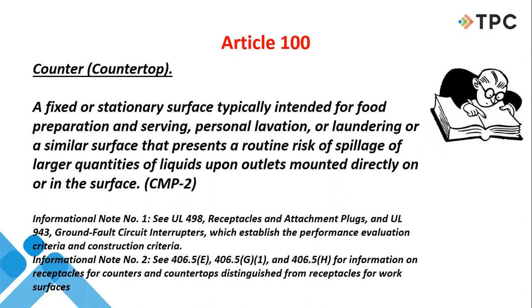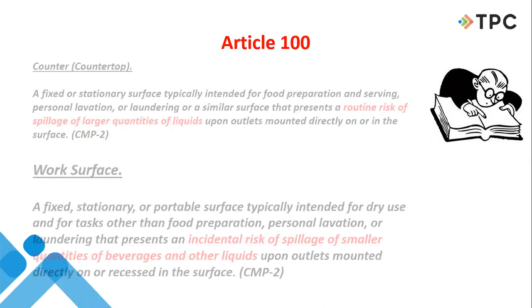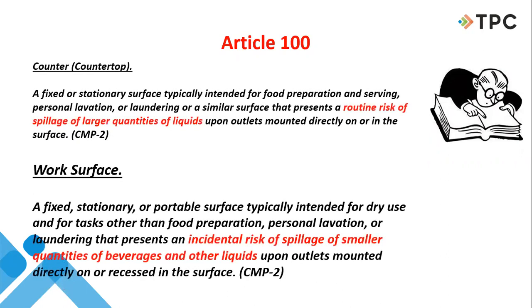They even mention at the bottom here certain informational notes, and they're referring you to certain UL standards regarding these particular receptacles and where they're evaluated or where they're approved or intended to be used and where they're not. But this is a countertop. Now, a work surface is a fixed, stationary, or portable surface, typically intended for dry use and tasks other than food prep.